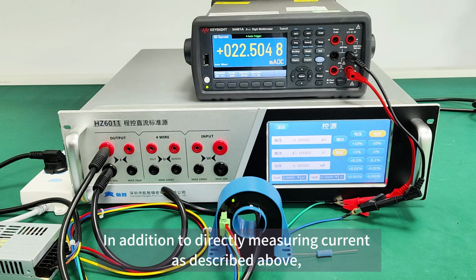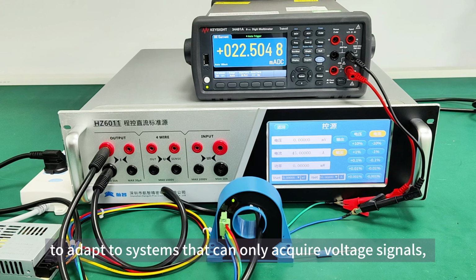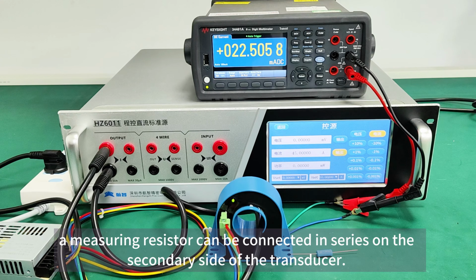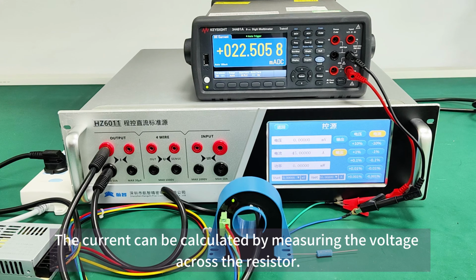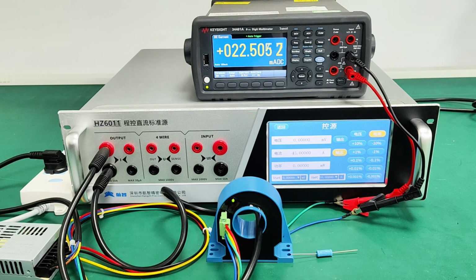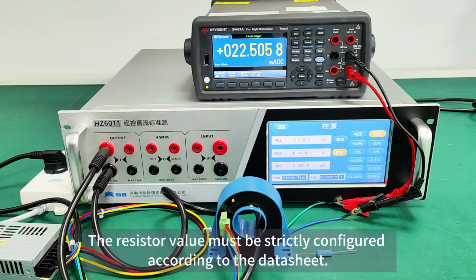In addition to directly measuring current as described above, to adapt to systems that can only acquire voltage signals, a measuring resistor can be connected in series on the secondary side of the transducer. The current can be calculated by measuring the voltage across the resistor. The resistor value must be strictly configured according to the datasheet. The datasheet indicates that the HIT500 can be configured with resistors from 0-5Ω.